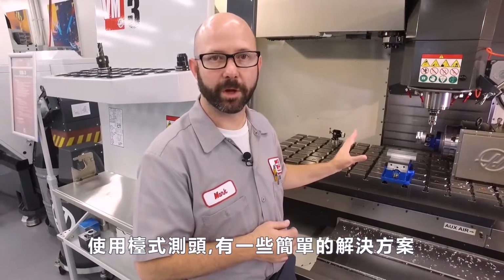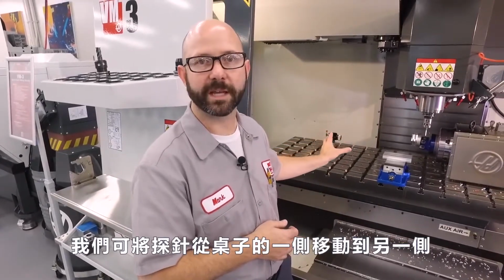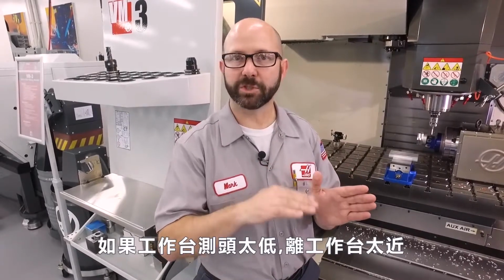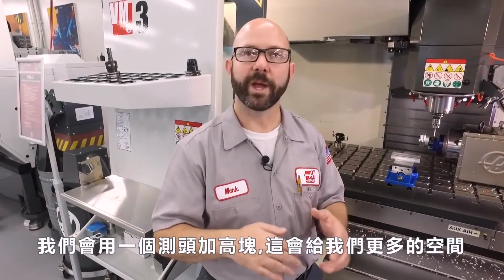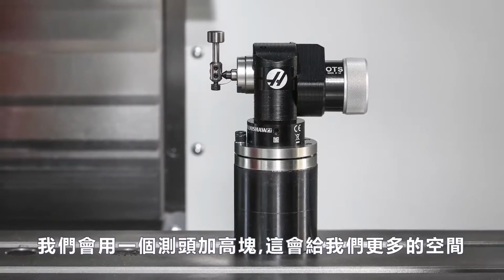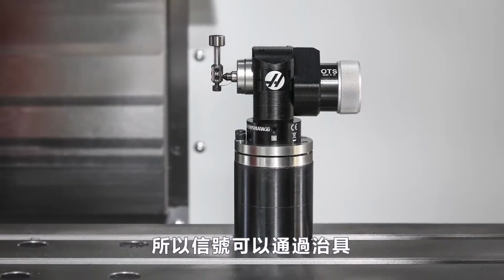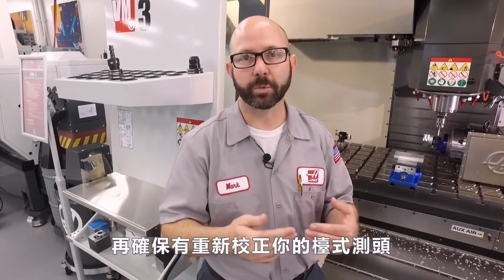Now, with our table probe, we've got some simple solutions. We can move that probe from one side of the table to the other, if that's going to solve our problem. If the table probe is just too low, too close to the table, we actually sell a probe riser block that'll give us some more clearance so the signal can get up and over that fixture. Just be sure to recalibrate that table probe when you're done.